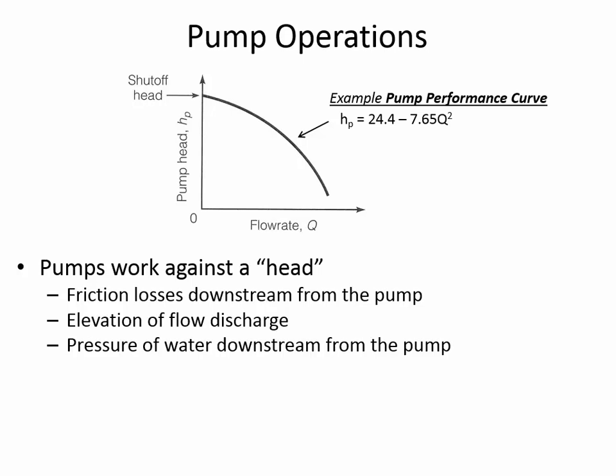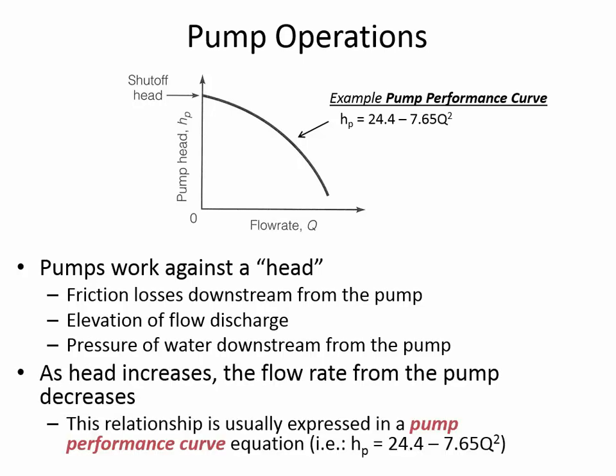It's also working against the elevation difference. And then it's also pressurizing the liquid. Sometimes you're wanting to lift it primarily. Sometimes you have a pump in place just to increase the pressure. Like if people are complaining about the water pressure being too low at their house, adding a pump isn't going to change how high the water is, but it's going to increase the pressure in the lines.